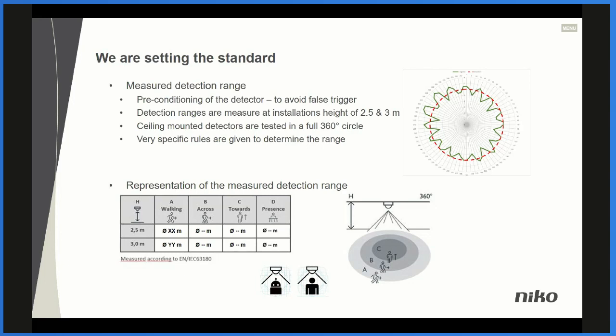Perfect. So the measured detection range is also shown like this in our product sheets. Before the detection range is measured, of course, the detector has some preconditions that need to be specified or configured, for instance, to avoid false triggers. But the detection range is also measured at installation heights of 2.5 and 3 meters. And I almost said, of course, because these are ceiling-mounted detectors, they are tested in a full 360 degree circle. And there are very specific rules, as I just mentioned before as well, to determine the range. If we could have a look, Torben, who is presenting right now, I'm not, at the upper right, we have an example of a measurement.